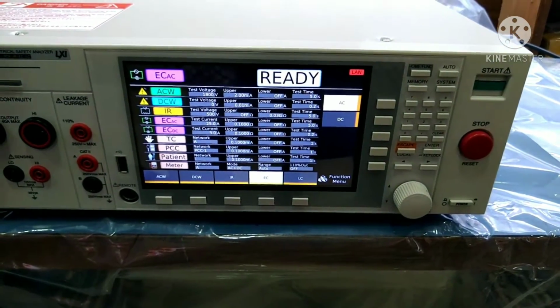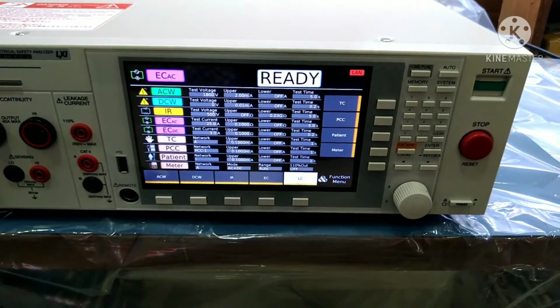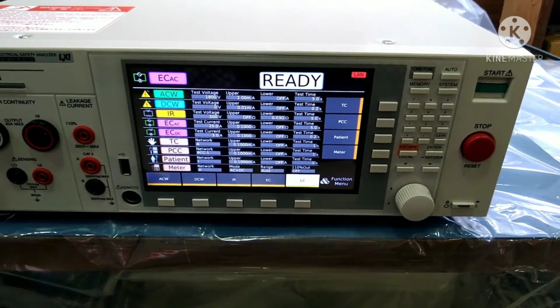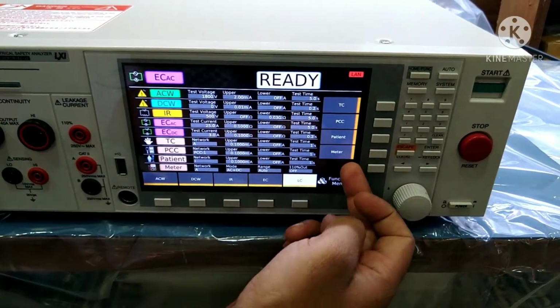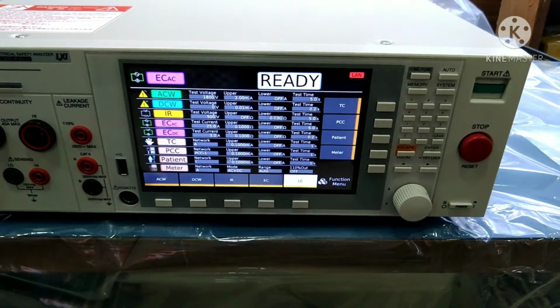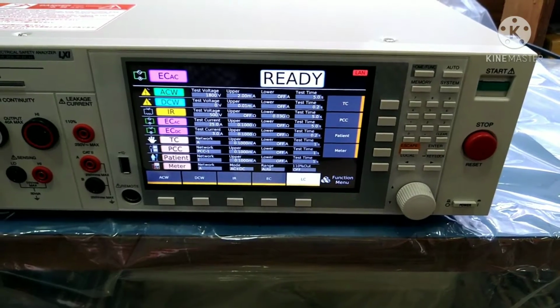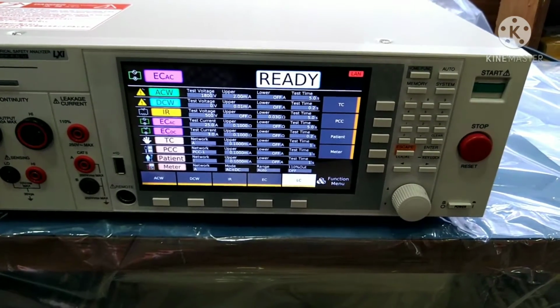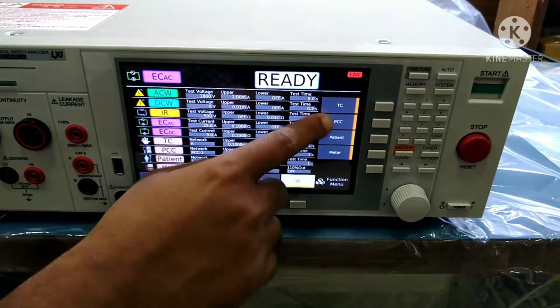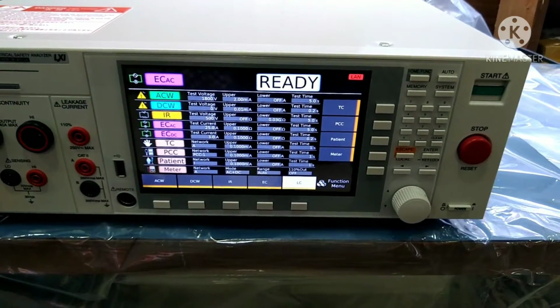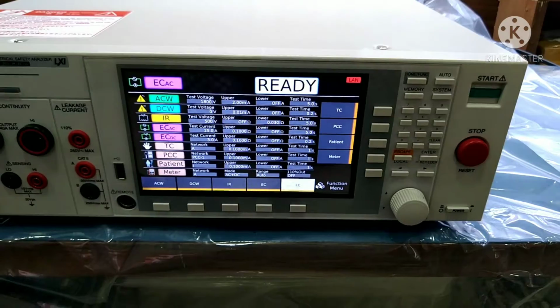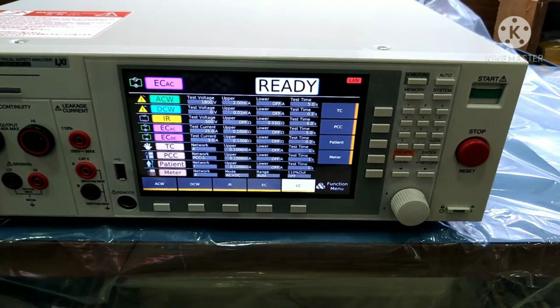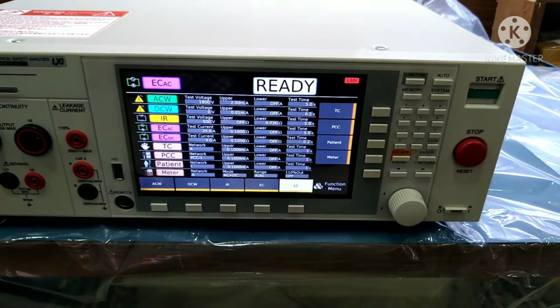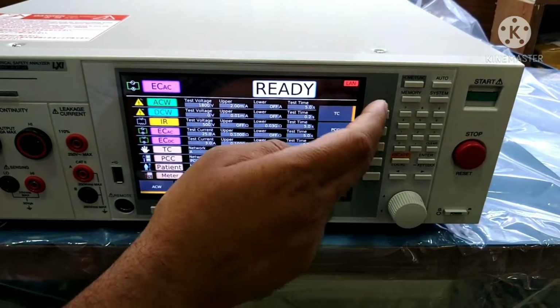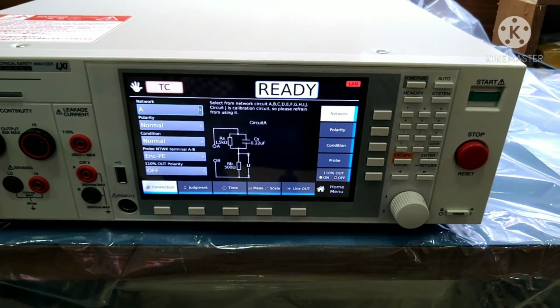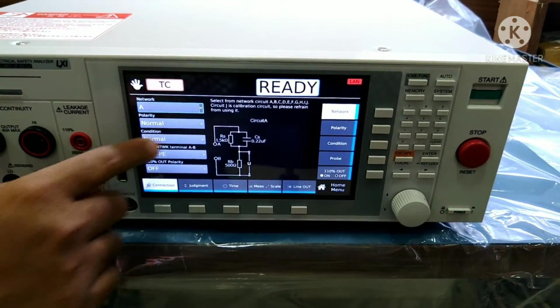Next we will discuss the LC. This is a very important part. Generally, we have two settings in this testing. One is TC, meaning touch current. The second one is PCC, meaning protective conductor current. So you can test both. In this case, we need to switch on the device. Right now I'm setting the TC. From TC, you can also select the network type.